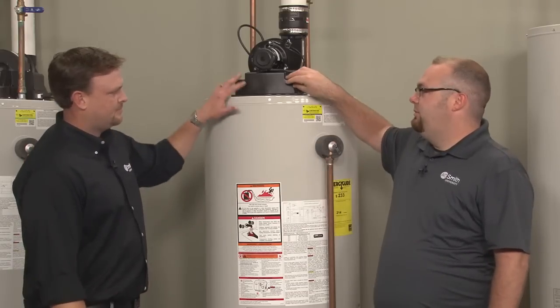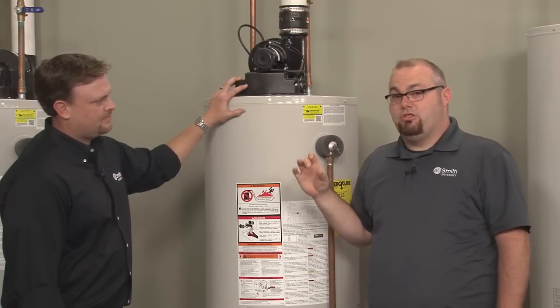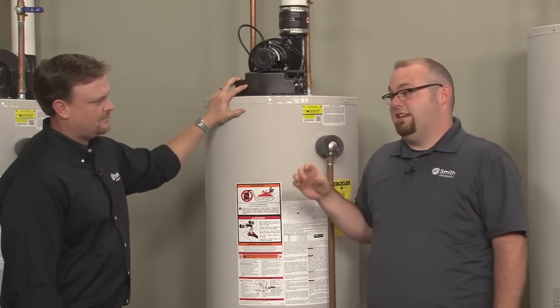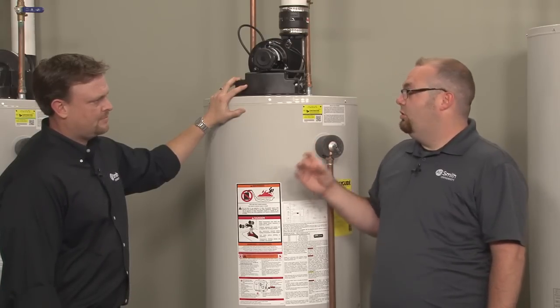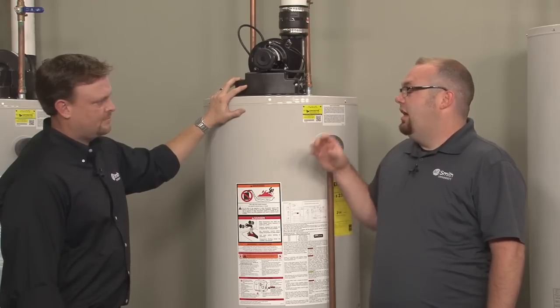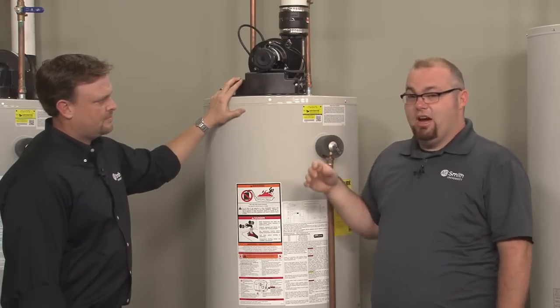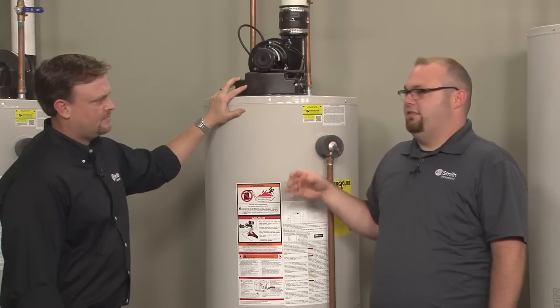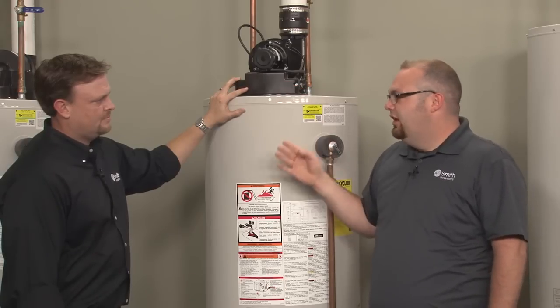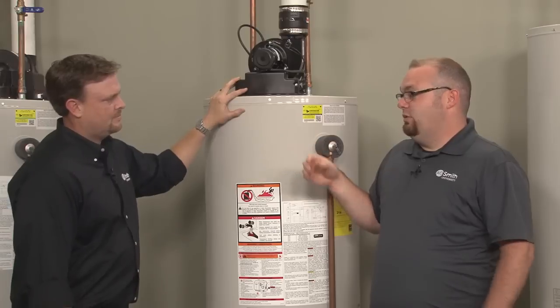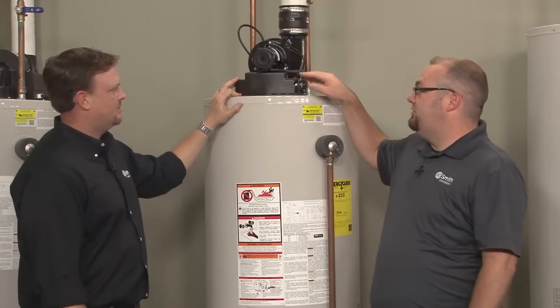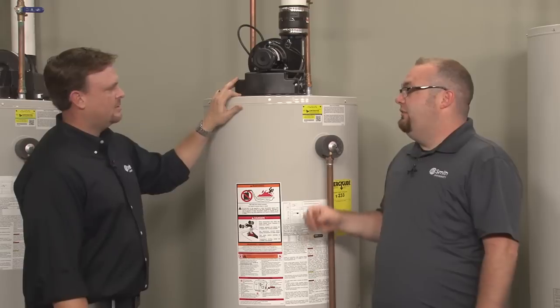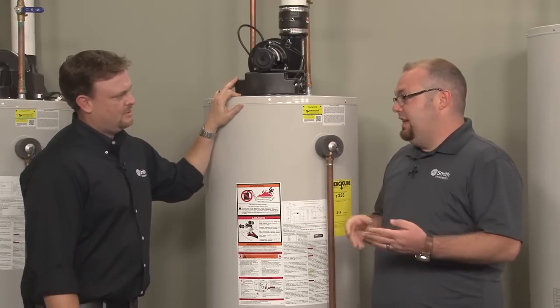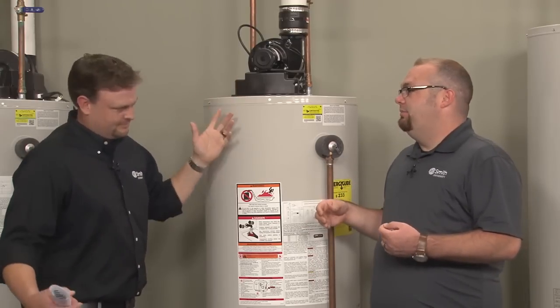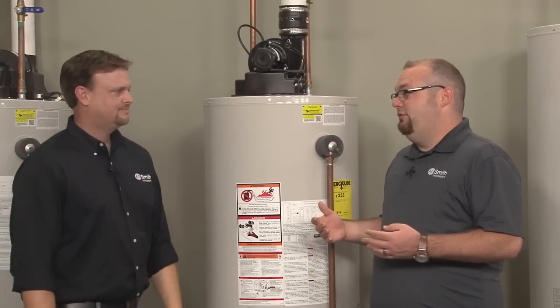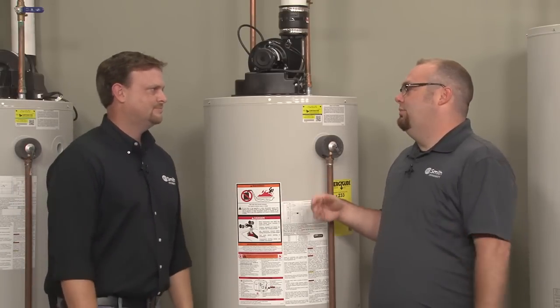So I remove my cover. I can actually look at the pressure switch on any of our power vents, and it tells you how much vacuum's required for that pressure switch to activate. So if I remove the cover, look at the switch, and the switch says it activates at negative 0.27, like on this model, that means with the digital manometer, I have to see how much vacuum my blower motor's pulling. If it's pulling more vacuum than is needed to activate that switch, the switch is bad. If it's not pulling enough vacuum and my venting and everything's good, then the blower motor would be bad.